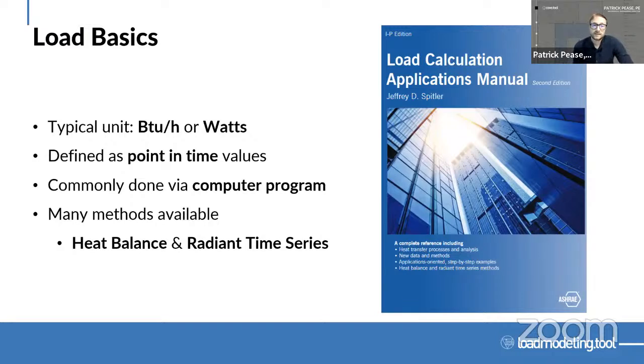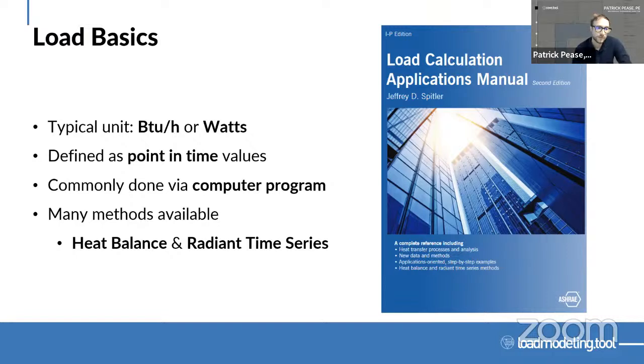Some quick load basics. In IP units we're talking BTU/h; in SI we're talking watts. Those are the primary units we're using — for example, 12,000 BTU/h in a room is the load I need to counteract. We're talking point-in-time when we talk about a load model — what's the specific time this peak load is happening? We're not looking at yearly results; that's more on the energy side. We're really asking what's the exact worst-case time for my project.